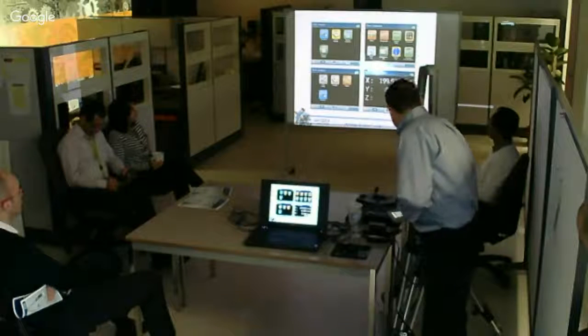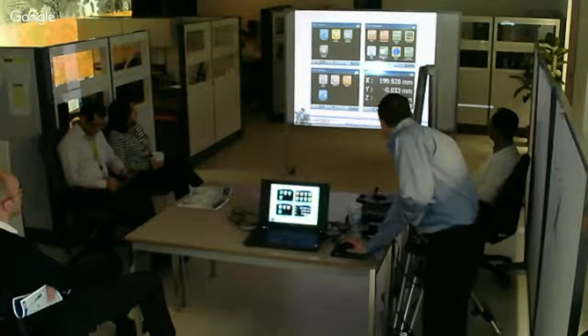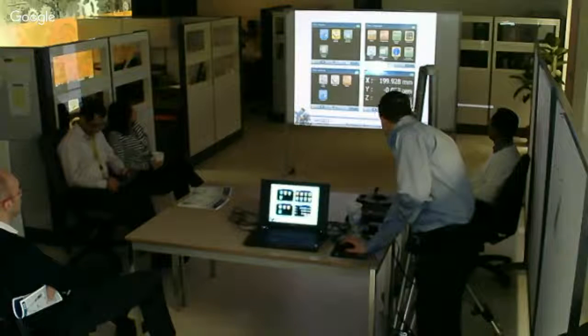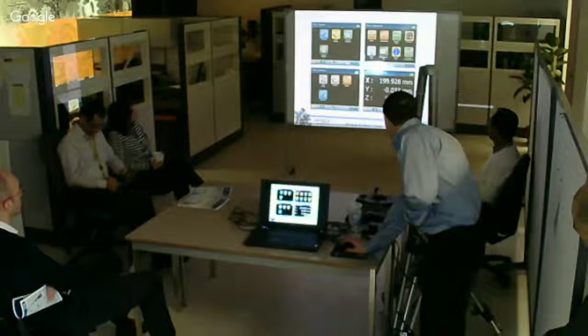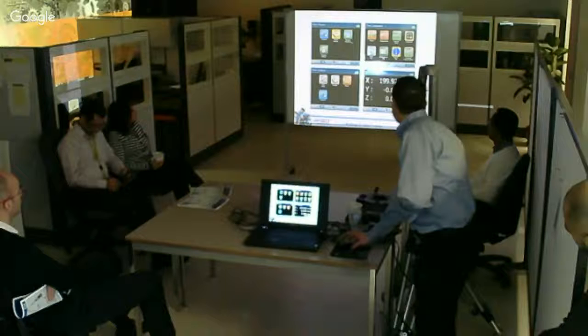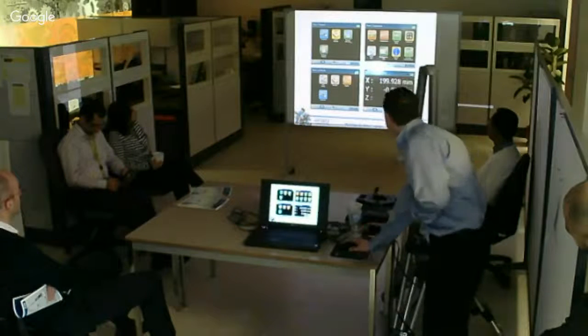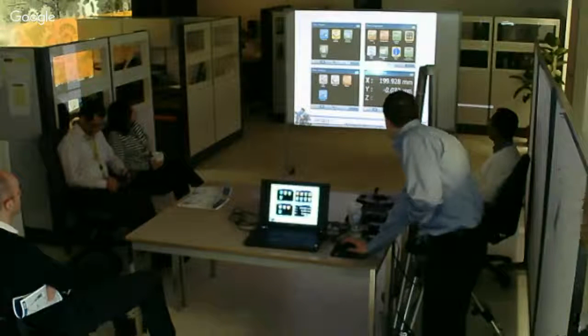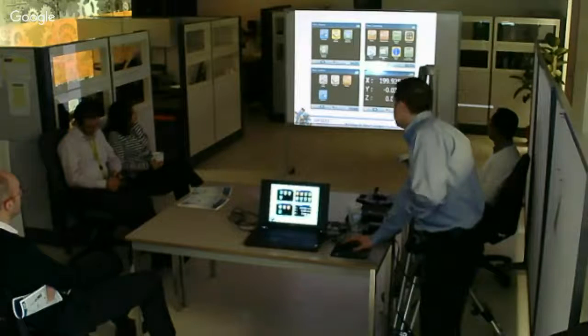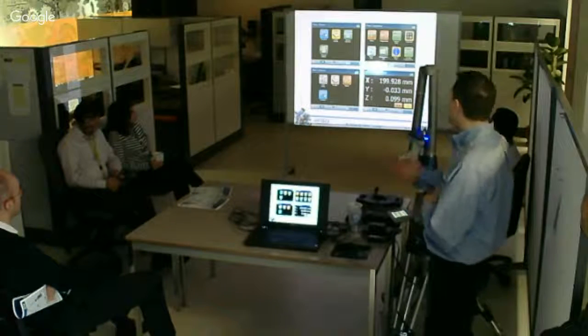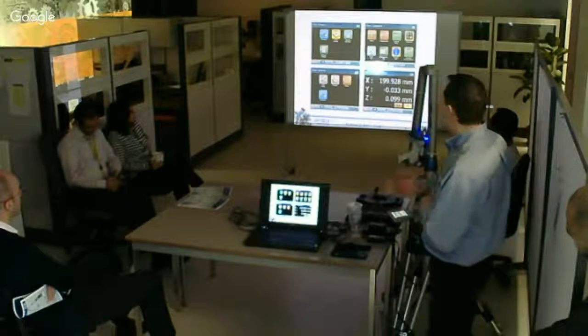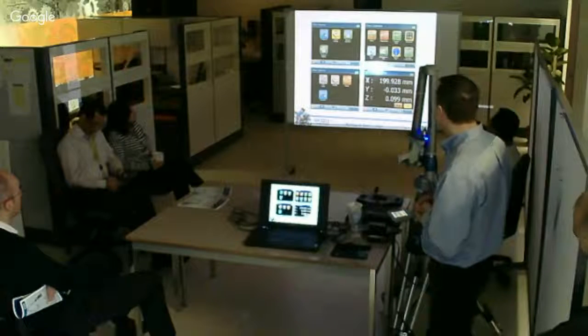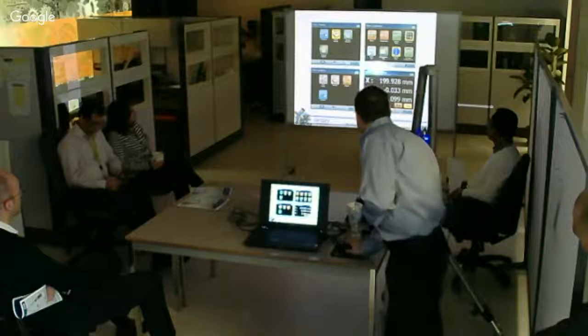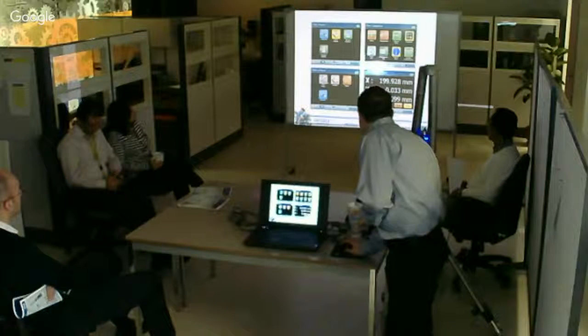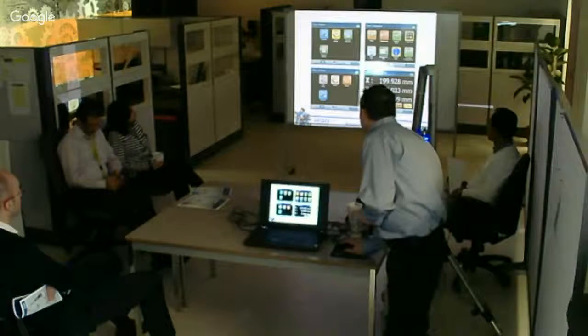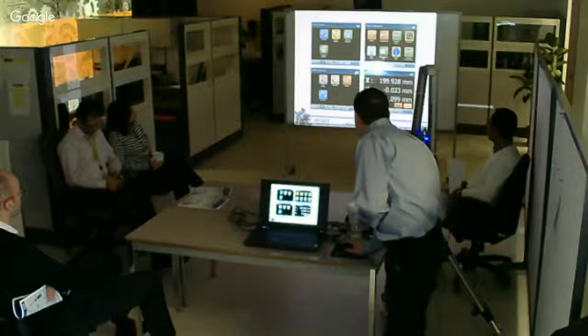So these are just various screenshots showing different features. You can do checks, I don't see it on this screen, but there are diagnostics to make sure your mount is level and your temperature is okay, plus event logs. So if there have been any changes, say you calibrated yesterday and want to go back to that calibration, you have the ability to do that, as well as take measurements between two planes or two points. I can do measurements there, check angles, etc.